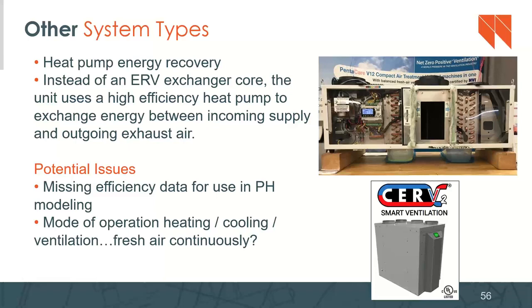It does talk a lot about the demand controls. So there's sensors involved with that system that are going to detect higher levels of CO2, I believe, higher levels of VOC. Those sensors are going to detect it and it's going to activate the ventilation system or run that ventilation system with more outdoor air. And so while that's not explicitly compliance with 62.2, at least not that I know, I think there's probably some benefits to using that demand side technology.